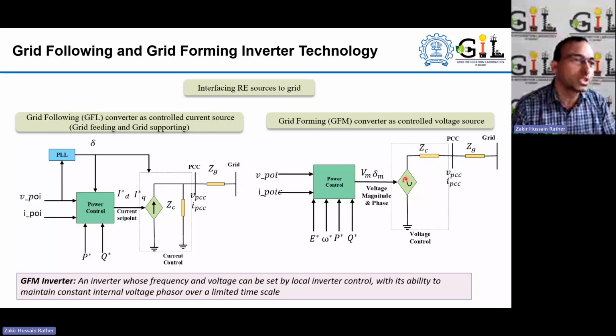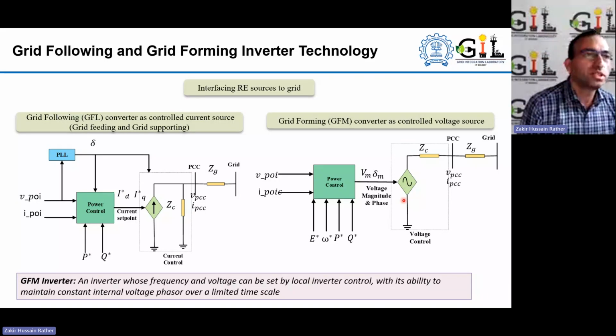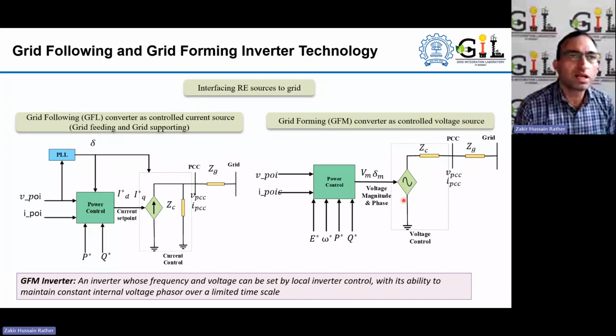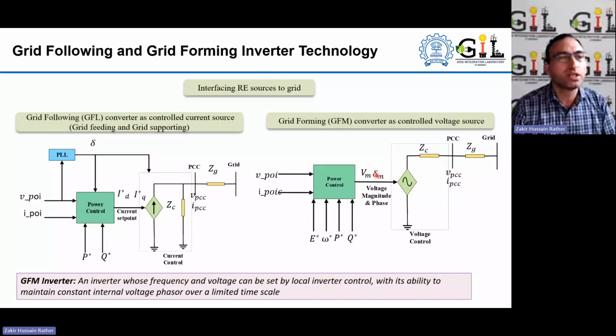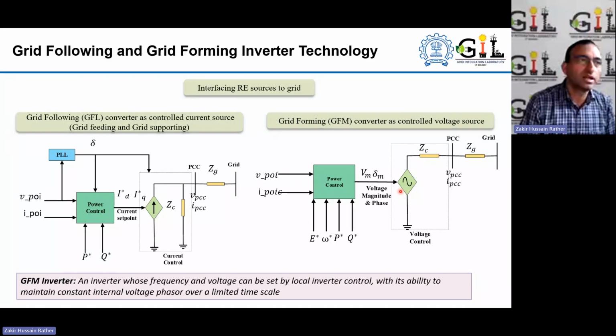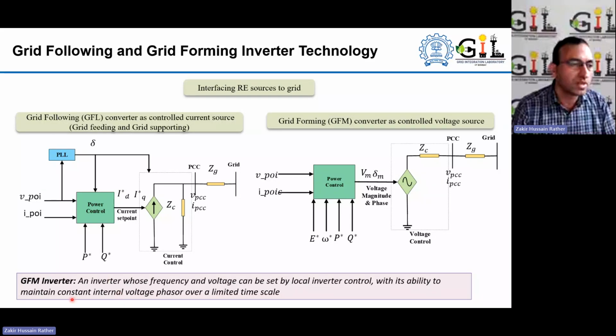So this operates as a voltage source technology rather than a current source, similar to exciter control in the synchronous generator, which controls the voltage. Here also the internal voltage is being controlled, and then the angle, corresponding to load angle control in the conventional synchronous generator, which we control primarily through governor control. Here also the voltage angle is controlled, with an internal voltage, an equivalent EMF, and then the angle is being controlled. So it behaves similar, not obviously identical, but similar to the conventional generator in its response characteristics. So that's essentially grid forming technology. There are several definitions of grid forming technology, but for the sake of simplicity, I have put this definition here.